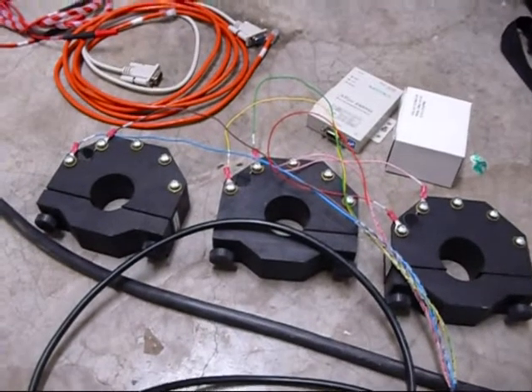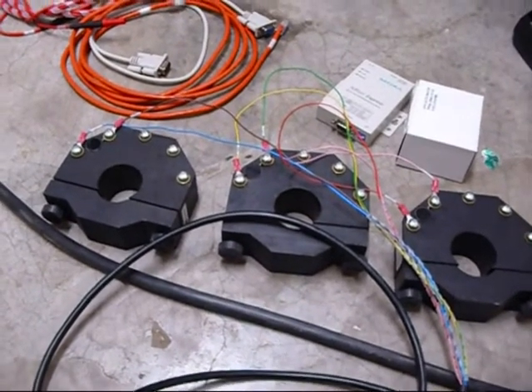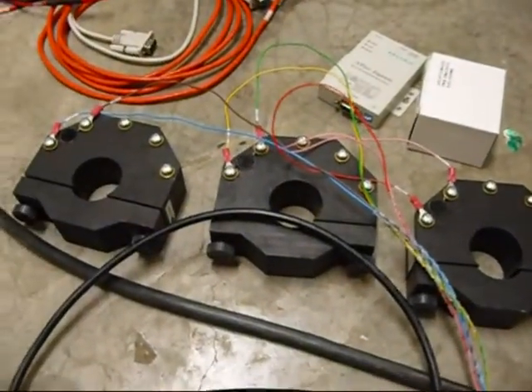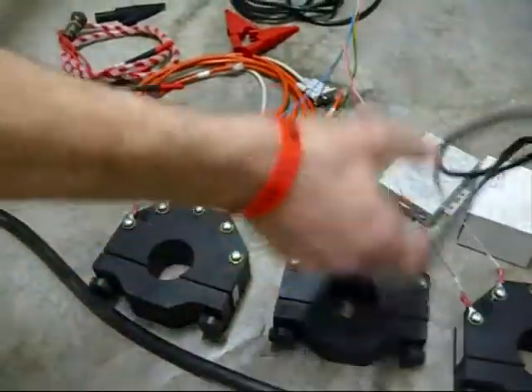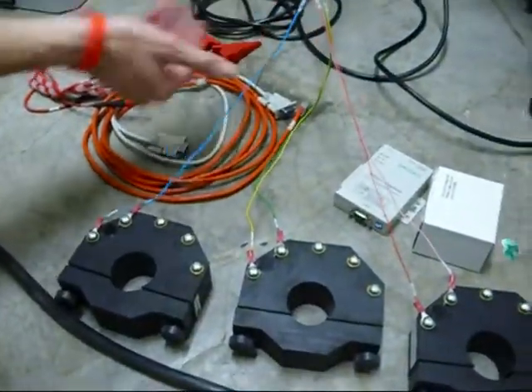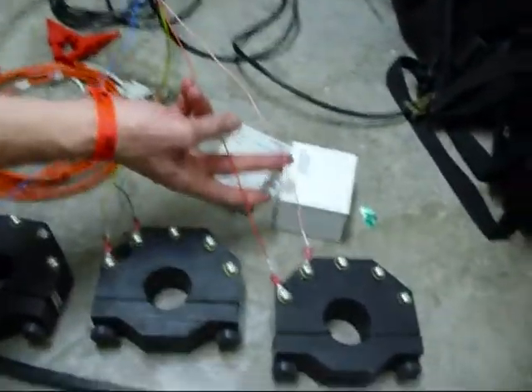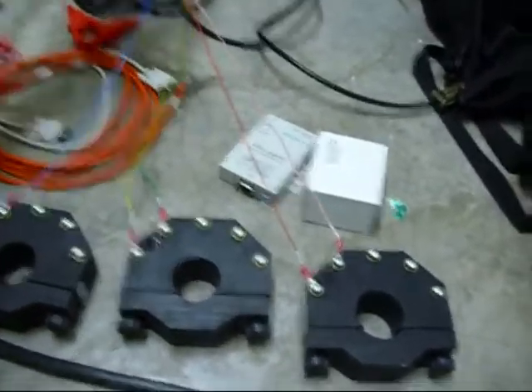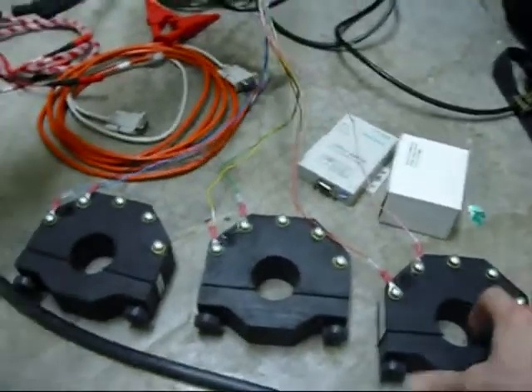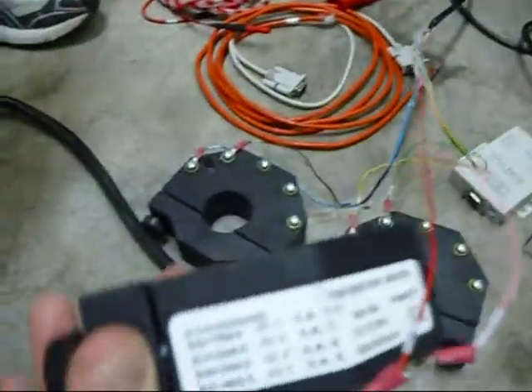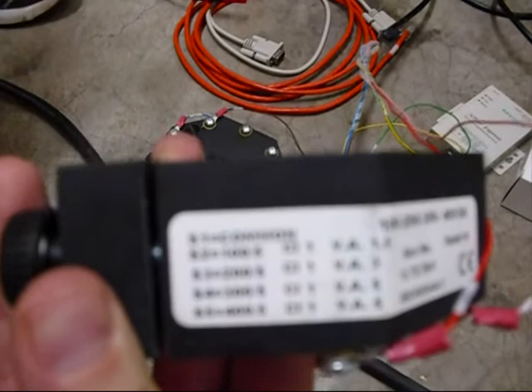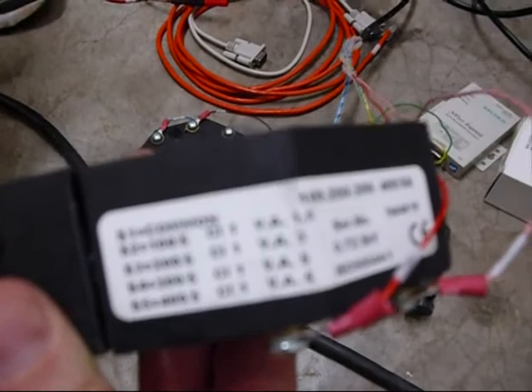What we're going to do now is we're going to connect the CTs. So as you can see, we have a CT cable and it has 3 pairs of cables. These are clearly marked as I11, I12, I21, I22 and I31, I32. Now, as mentioned previously, we've connected these across S1 and S2. There's a label on the side of the CT that we can read. It says that S1 is the common, and S2, S3 and S4 are to select different primaries. In this case our primary is 100 amps, so we've selected S2.